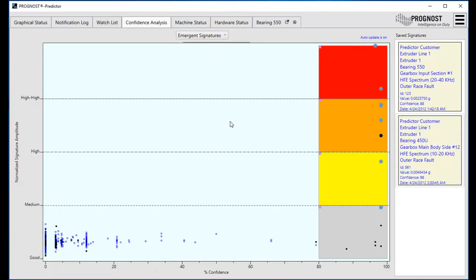The database contains thousands of signature trends. The confidence analysis is a data mining tool to identify particular signature trends needing attention, saving the exhaustive inspection of every trend. Points in the probable fault region are usually early faults where the threshold should be evaluated and possibly lowered. Points in the upper left corner should have their thresholds evaluated because the thresholds are possibly too low. It is good practice to regularly tune the thresholds by using this tool to identify which signature trends need adjustment.